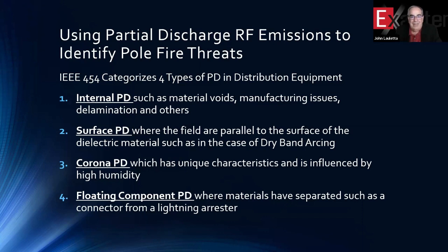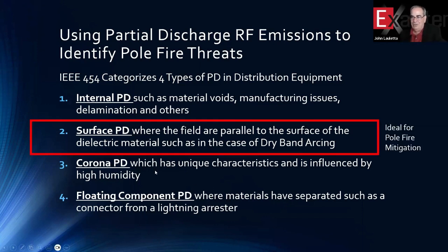And of course that high impedance connection is going to go into partial discharge. But what we really like is the surface PD issue, because it's a perfect one to mitigate pole fires by detecting and analyzing, locating the source, and then mitigating the problem.